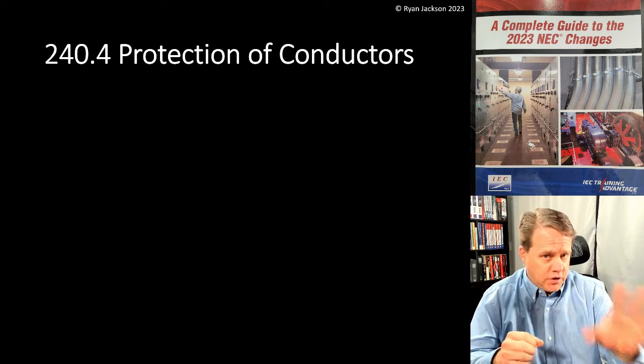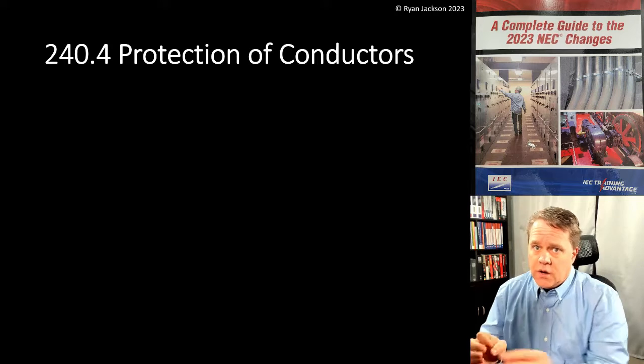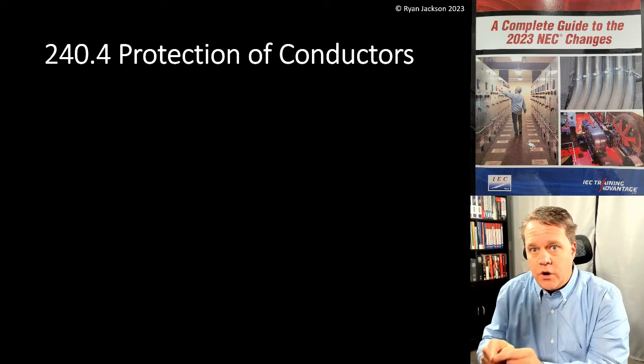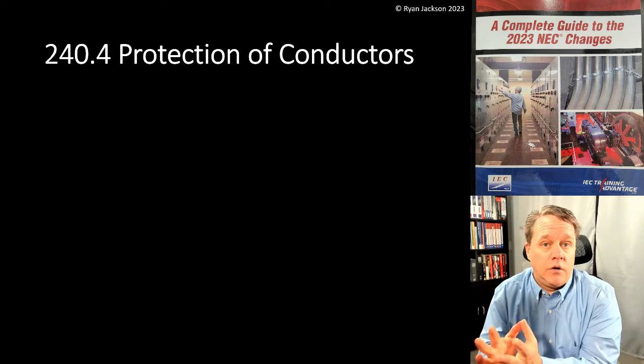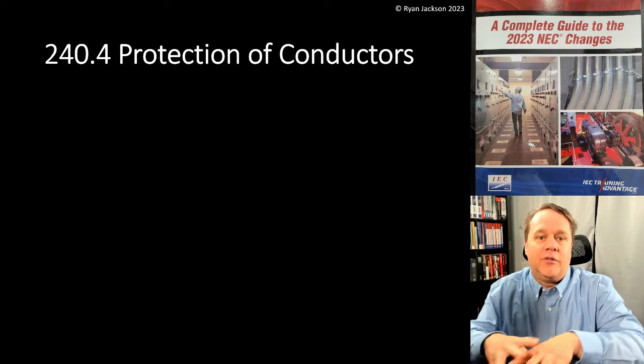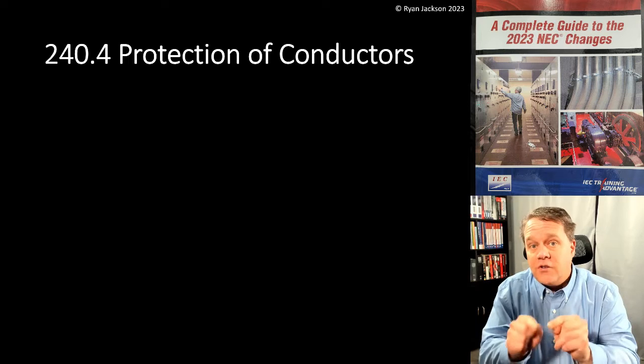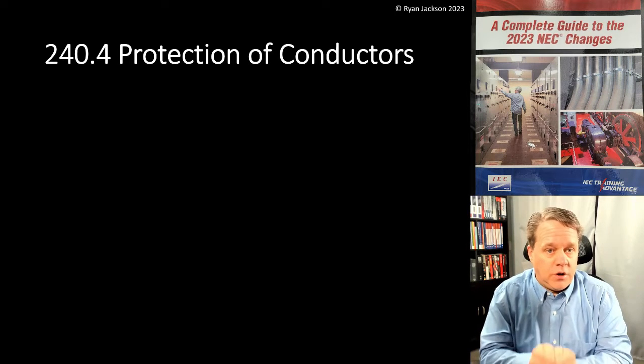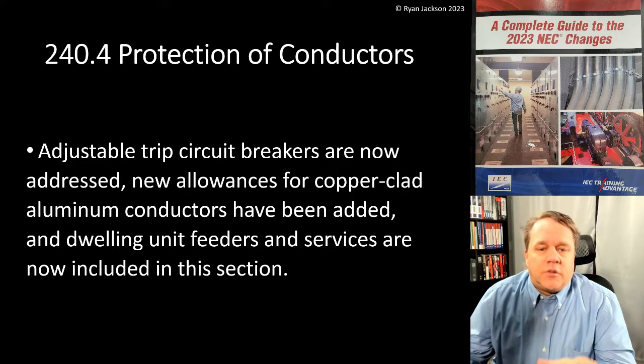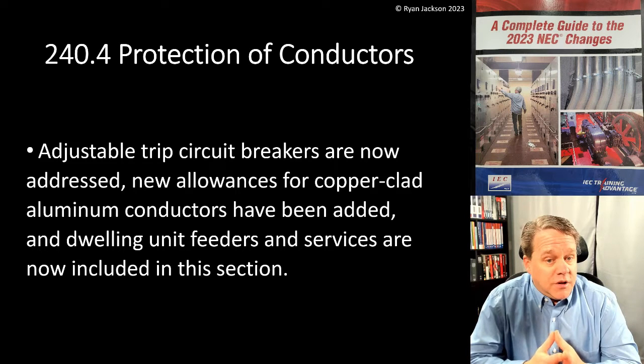Overcurrent protection is required for conductors and for equipment. We provide overcurrent protection for equipment in the equipment articles — Article 422 for water heaters, Article 450 for transformers — but the conductors themselves are taken care of here in 240.4. This is a really important section. Adjustable trip circuit breakers are now addressed, new allowances for copper-clad aluminum conductors have been added, and dwelling unit feeders and services are now included.